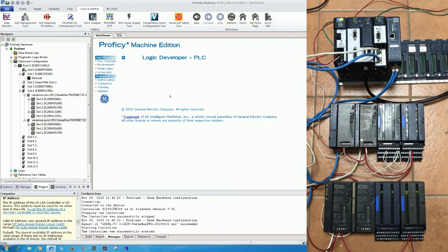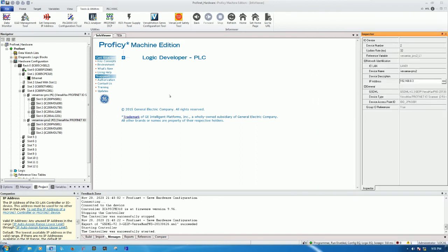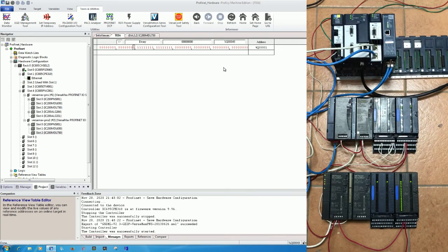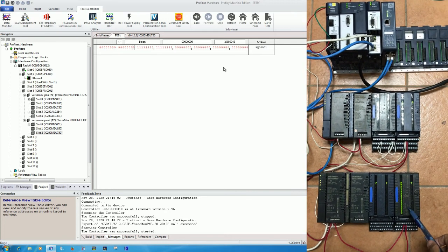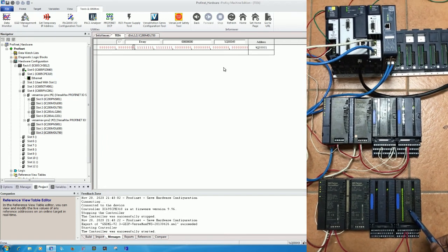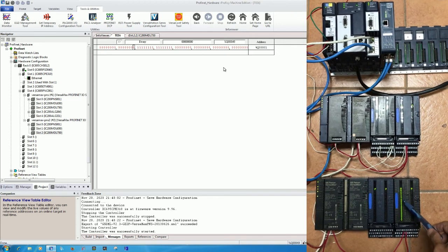Let's test the IO for confirmation. This one starts from %Q number 32. Let's go to test and then force 33. I will force 8, 9, 10, 11, 12, 13, 14, 15, and 16. Let's see the status on the PLC. Right now you see the points are on for digital output because I already forced the signal from our software.